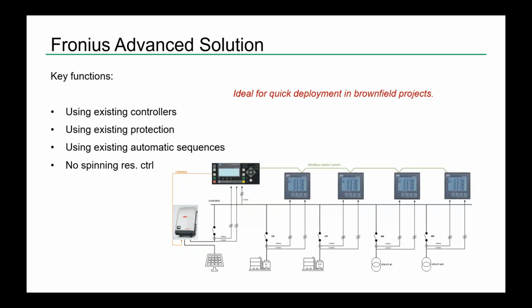Notice the advanced solution is ideal for quick deployment in brownfield projects or retrofit projects. It uses the existing controllers, so whatever you have on your generator will remain in place. Also, the protection remains in place. This means the automatic sequences that you already have in your existing system are the same after the installation of the PV. So this is one of the reasons why it's very fast to install, and you only have to focus more or less on the PV side and then install the measurement equipment.